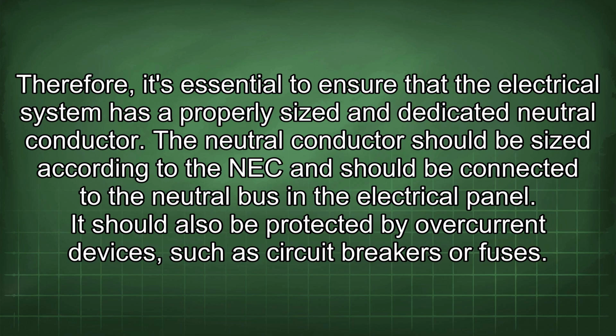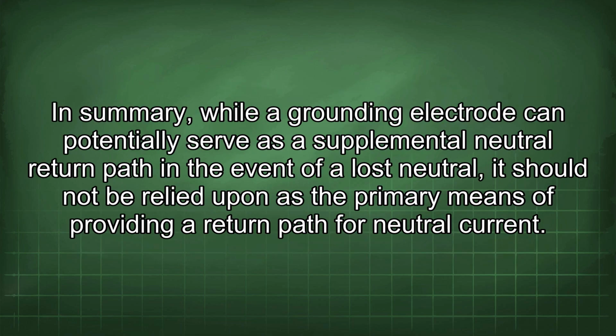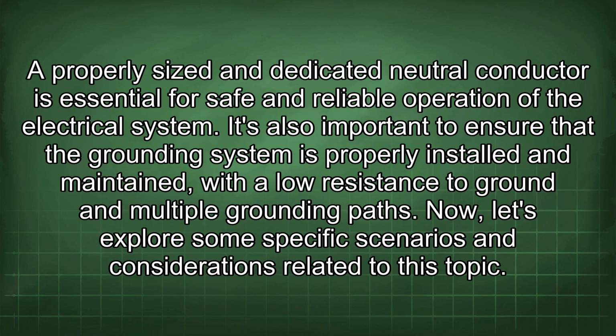The neutral conductor should be sized according to the NEC and should be connected to the neutral bus in the electrical panel. It should also be protected by overcurrent devices, such as circuit breakers or fuses. In summary, while a grounding electrode can potentially serve as a supplemental neutral return path in the event of a lost neutral, it should not be relied upon as the primary means of providing a return path for neutral current. A properly sized and dedicated neutral conductor is essential for safe and reliable operation of the electrical system.